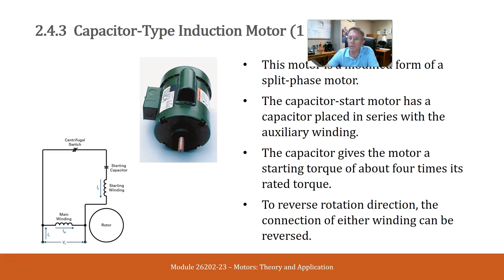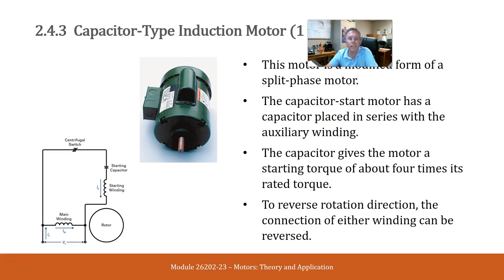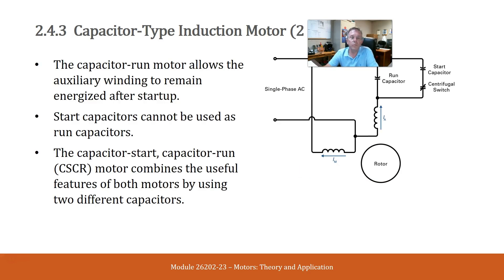On a capacitor type induction motor, this motor is a modified form of a split phase motor. The capacitor start motor has the capacitors placed in series with the auxiliary windings. The capacitor gives the motor a starting torque of about four times its rated torque. To reverse rotation, the connection of either winding can be reversed. The capacitor run motor allows the auxiliary windings to remain energized after startup. Start capacitors cannot be used as run capacitors. The capacitor start, capacitor run — or CSCR — motor combines the useful features of both motors by using two different capacitors.